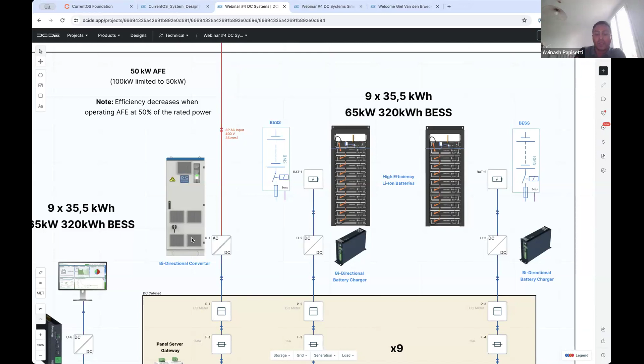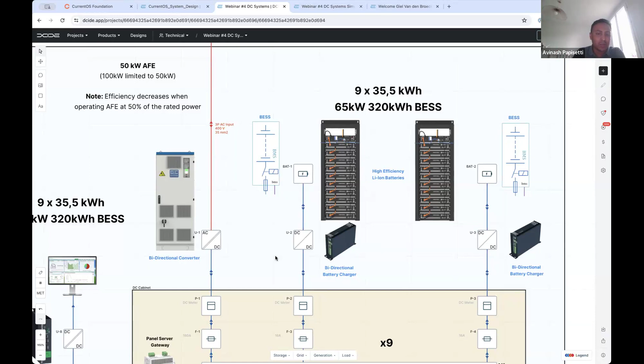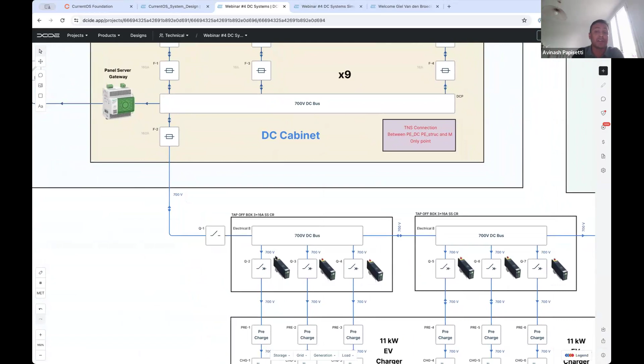For example, here you see a 50 kilowatt active front end, and just on the right side is the energy storage system, which is 65 kilowatt. So I have a 50 kilowatt gateway but a bigger energy storage with bigger power delivery. Going further down, there are electrical vehicle chargers connected on the DC bus, on the extended DC bus. There are 11 kilowatt chargers, 6 of them, summing to approximately 66 kilowatt of power delivery, plus some auxiliary power for lighting in the area.